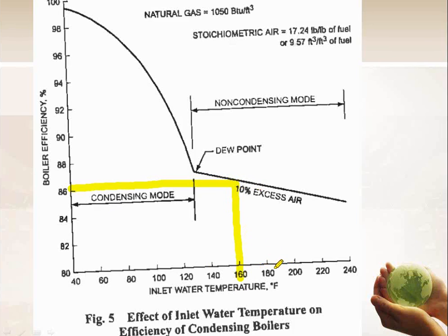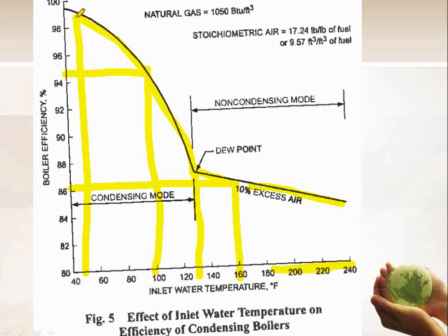Everybody's happy. If I ask for some hotter water temperatures, then as you can see, my efficiency is going to decline slightly. If I ask for some cooler temperatures, my efficiency is going to go up slightly. When I get to this point here, which is approximately 130 degree return water, my efficiency spikes up very dramatically, right? I get these very high efficiency percents. If I ask for 100 degree water, assuming my line is straight, I basically have a 94, 95% efficient boiler. If I say, hey, give me 50 degree water, my 86% boiler starts operating like a 99% boiler in this example, right?